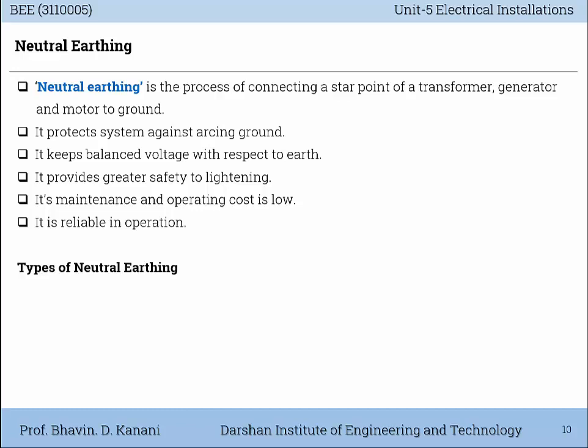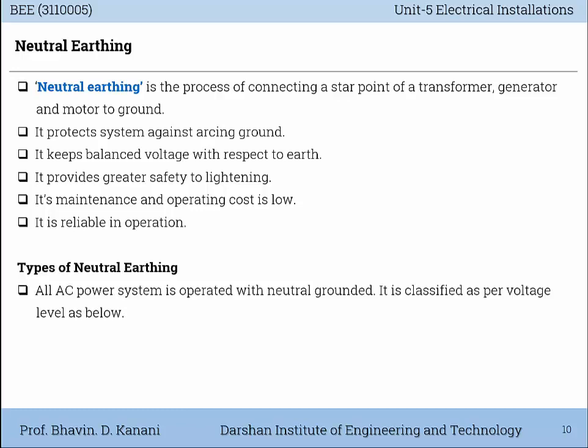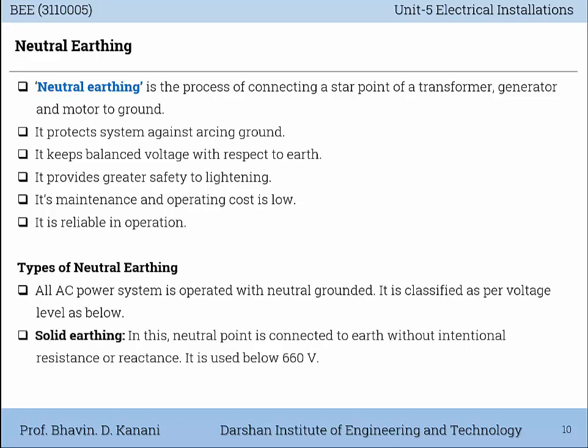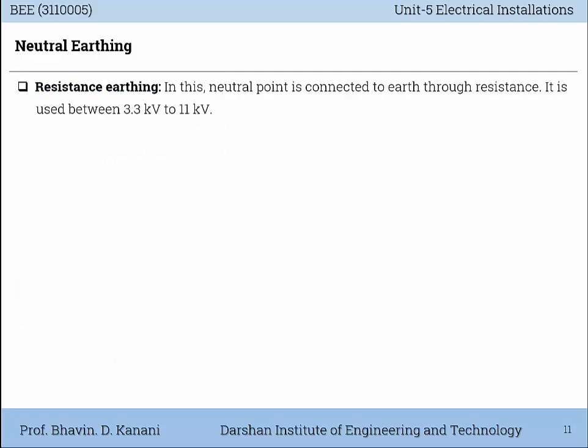Types of neutral earthing. All AC power systems are operated with neutral grounded. It is classified as per voltage level as below. First is solid earthing. In this, the neutral point is connected to the earth without intentional resistance or reactance. It is used below 660 volt. Next is resistance earthing. In this method, the neutral point is connected to the earth through resistance. It is used between 3.3 kV and 11 kV.